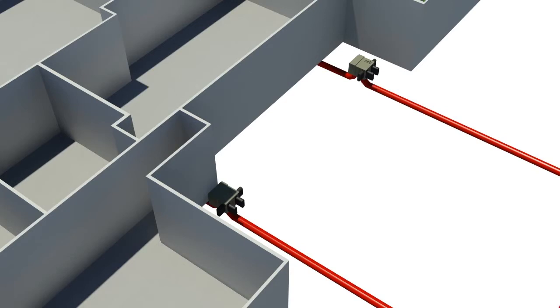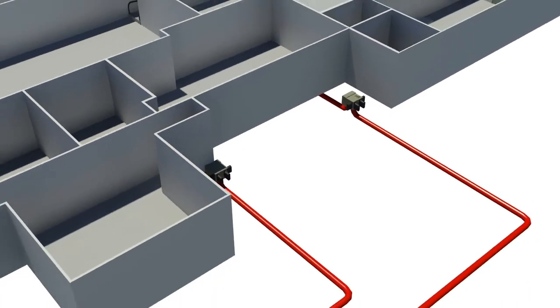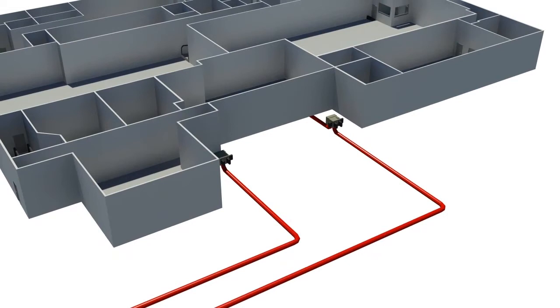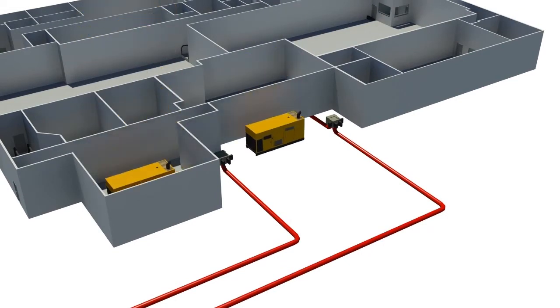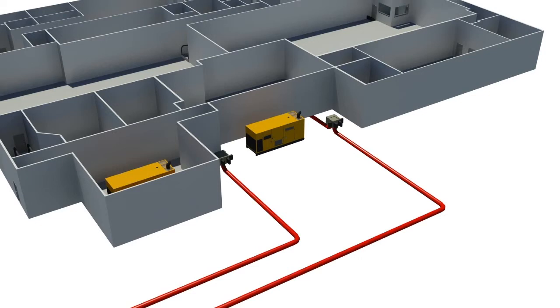In the unlikely circumstance that commercial power from both feeds to the site are temporarily disabled, these systems are supplemented by three generators: one 1,000 kW with a 1,000-gallon diesel fuel tank and two 800 kW Caterpillar diesel generators, and 5,000 gallons of diesel fuel on site which can power the center for as long as needed.